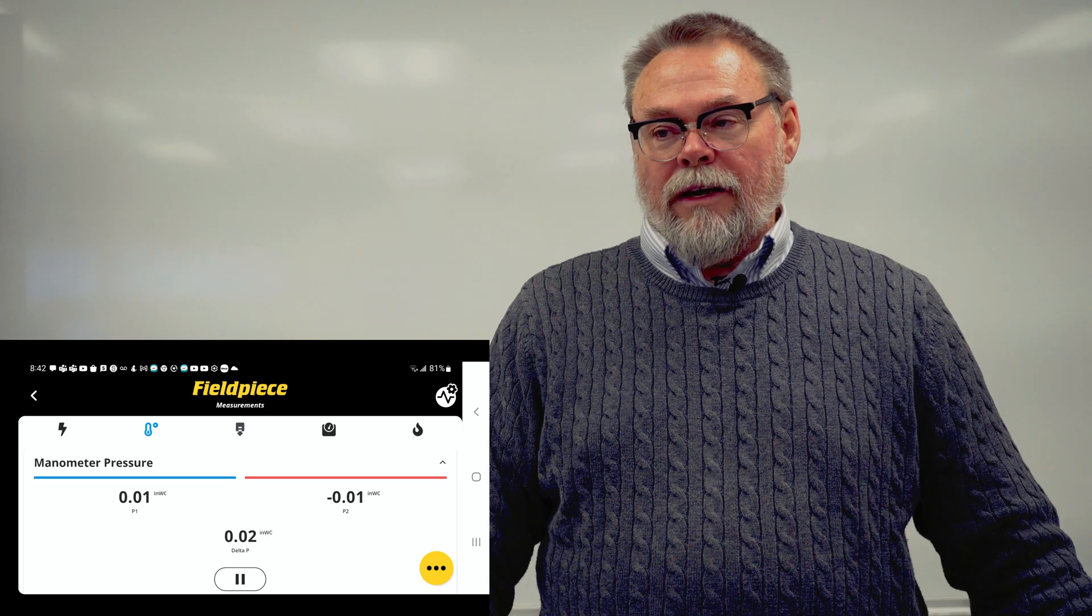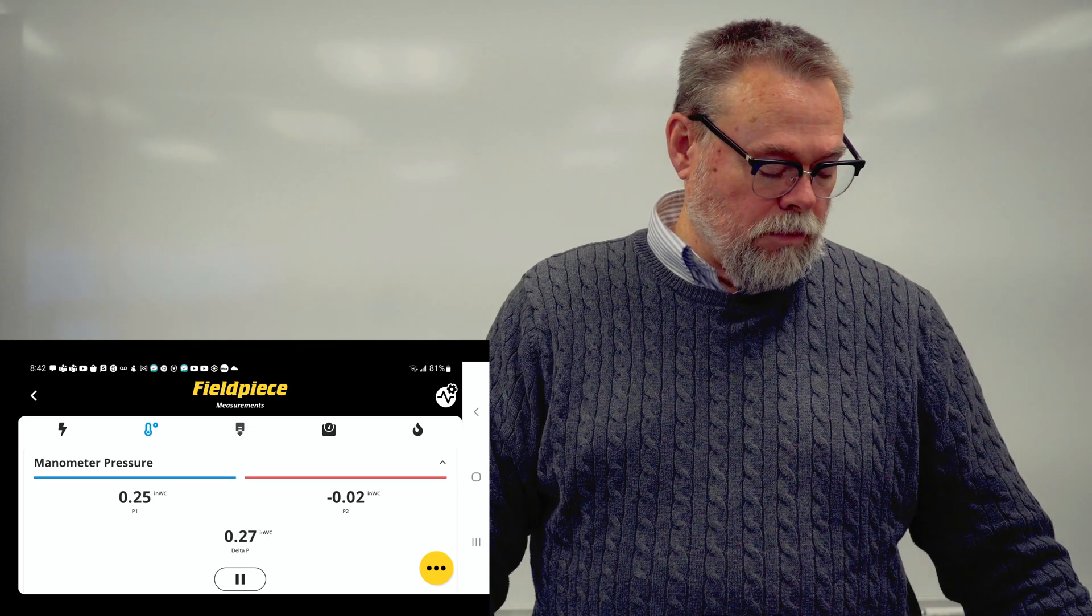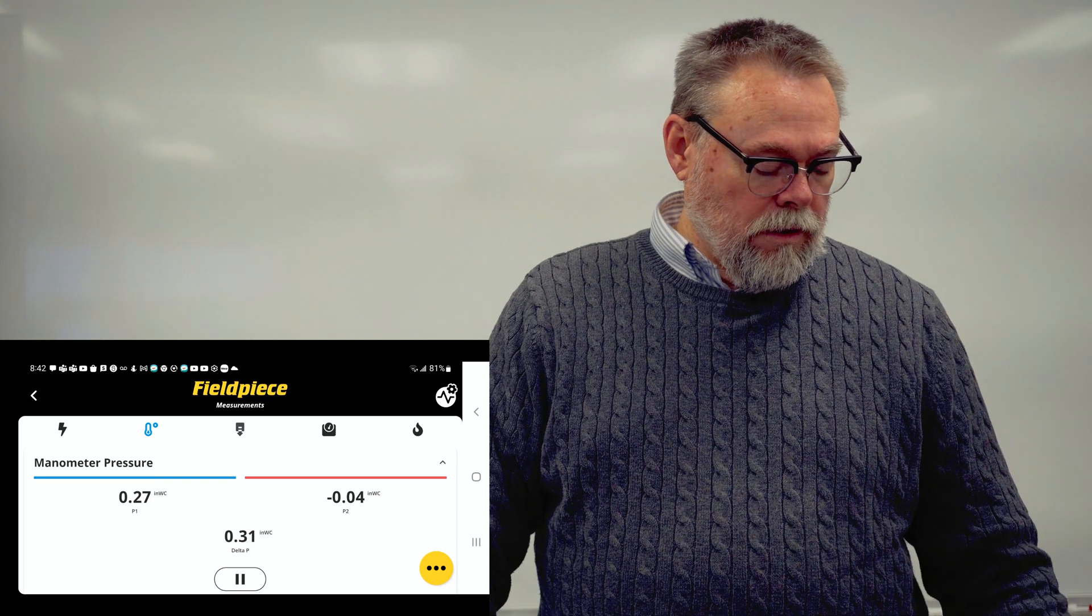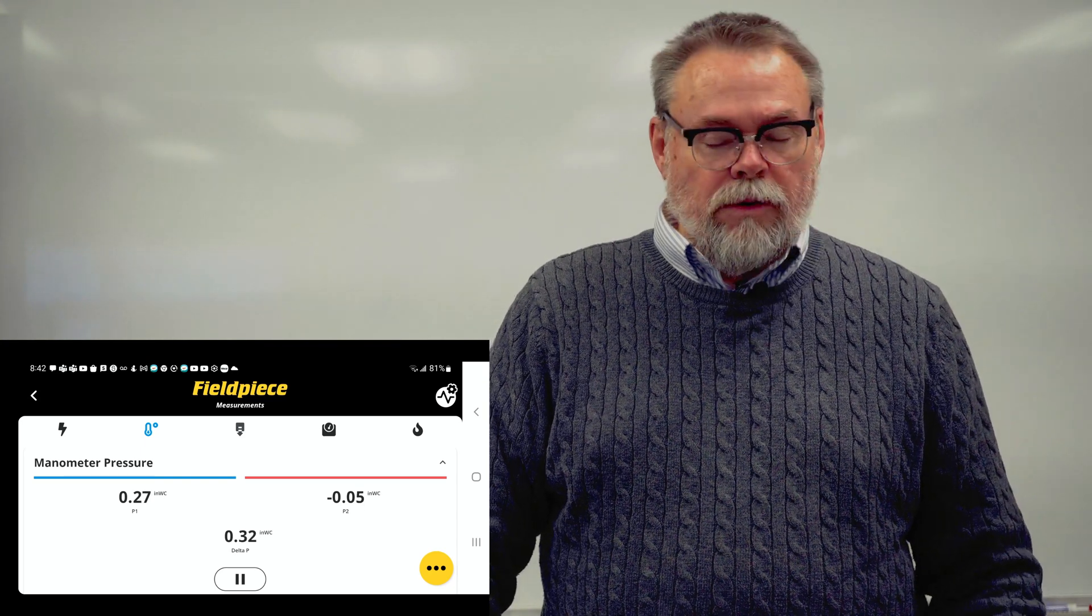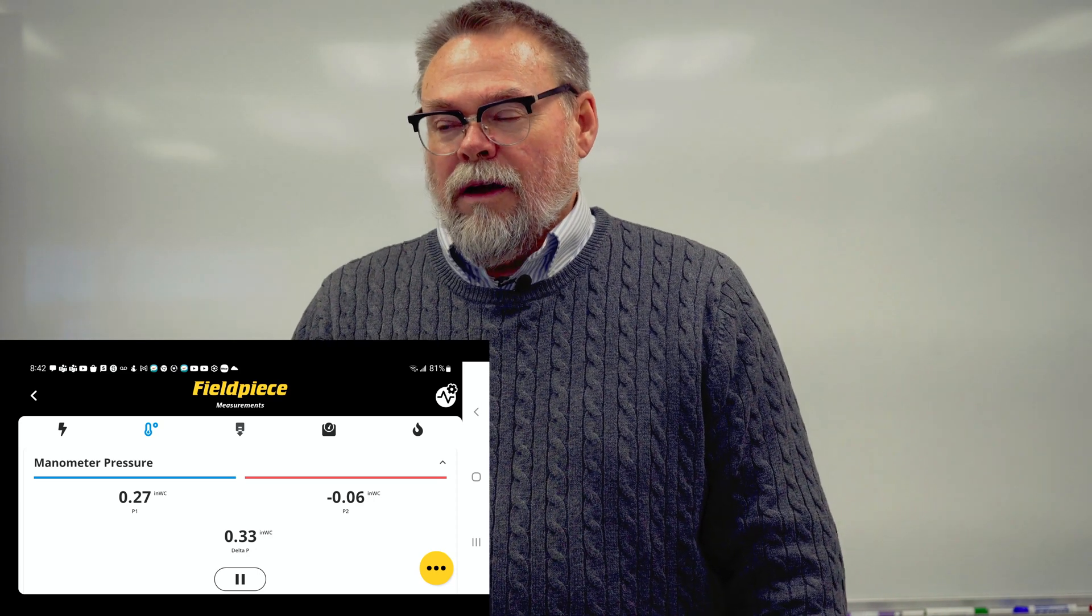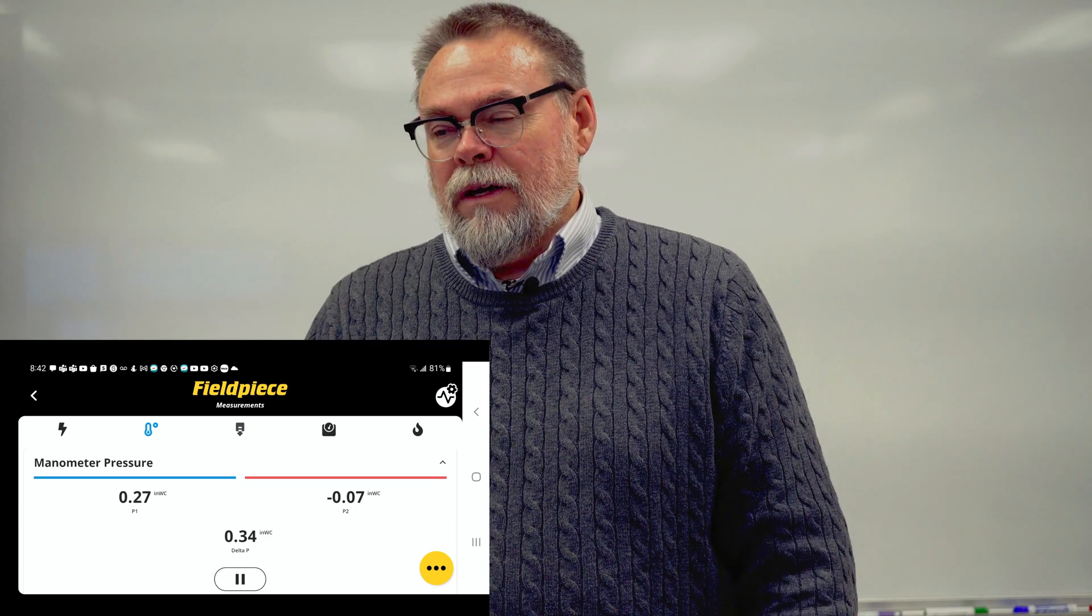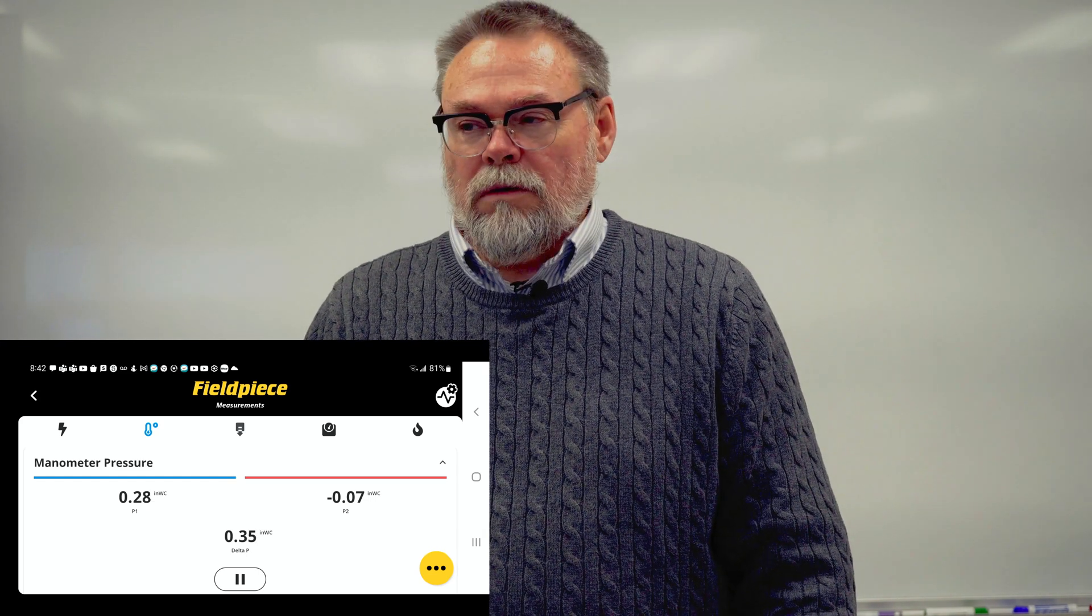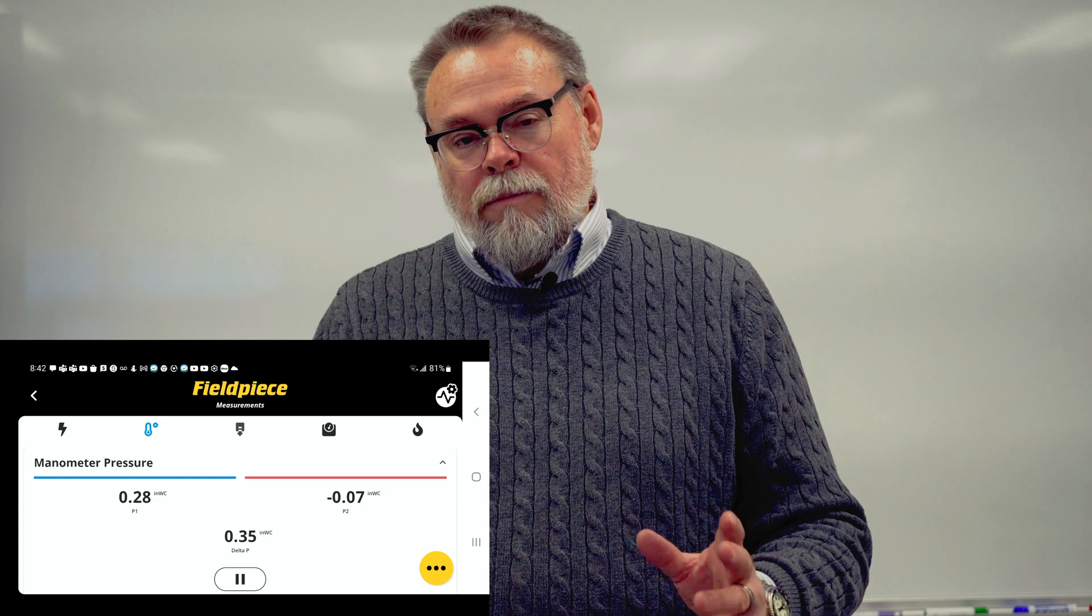Watch our static pressure start to rise. So there's one on the supply side, that's reading 0.24, 0.26, and 0.3, 0.4 on the other side. So it looks like we're going to be about 0.33, 0.34 probably. It's running full bore. So it's steadied out at 0.35.